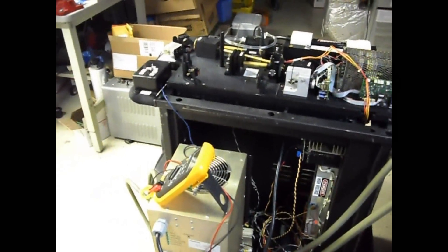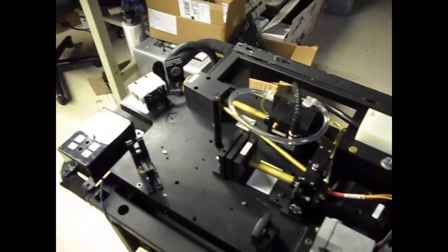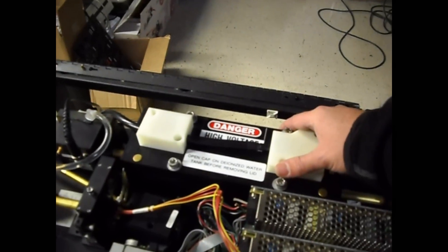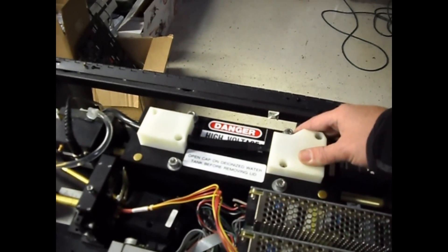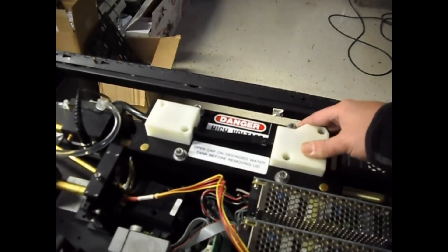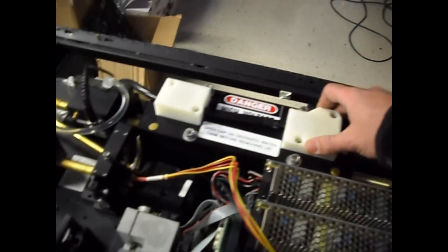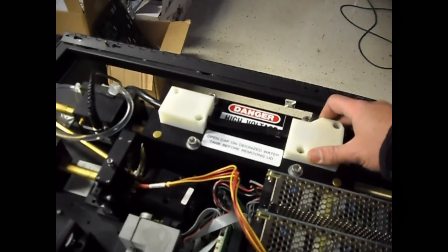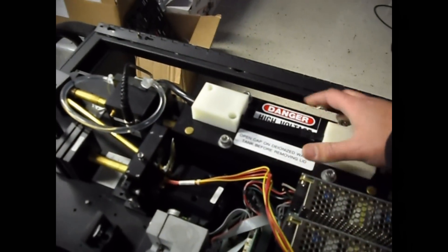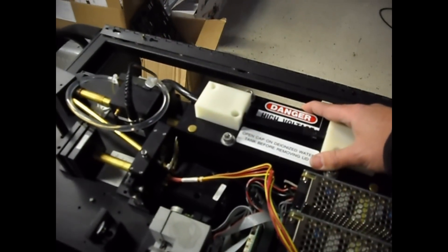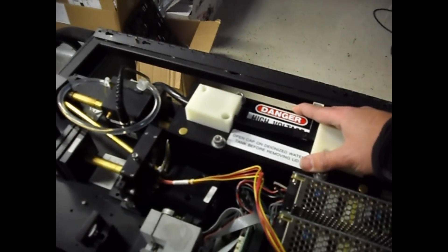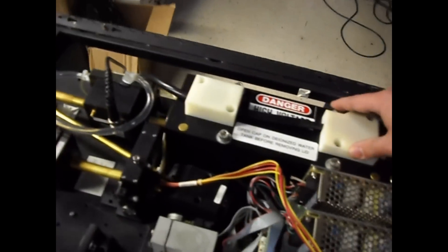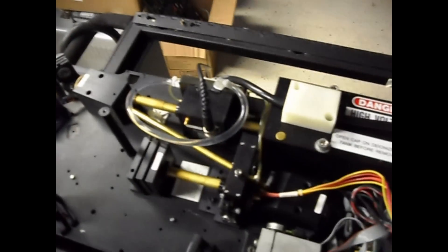First we'll start off with the head of the unit. As you can see right here, here's the top of the head or the business end of the laser. This right here is the YAG laser module. It basically has a very high powered lamp inside of it, kind of like a street light. It's an arc lamp which means it continuously arcs on like a flash lamp and produces about four or five thousand watts of light inside of this box. In here is a mirrored cavity which basically takes the light and sends it to the YAG rod which is located inside of the head.